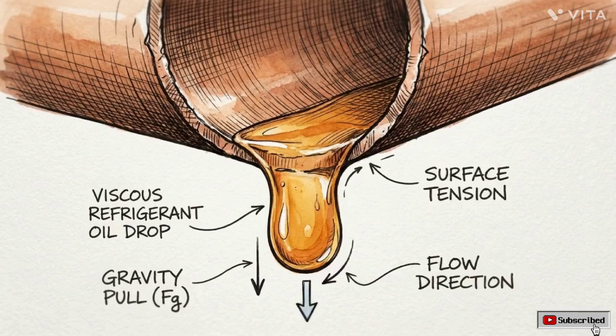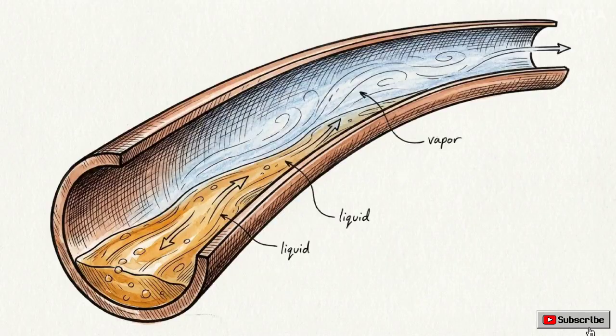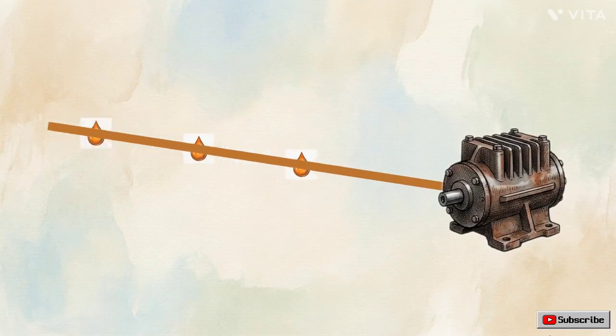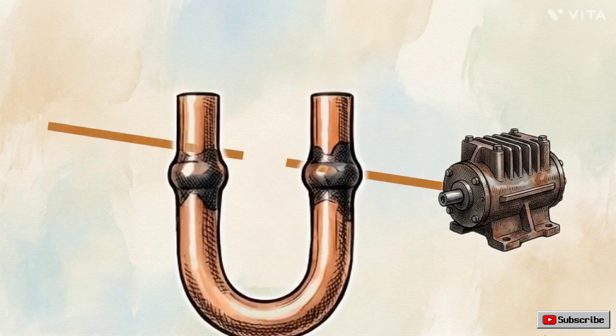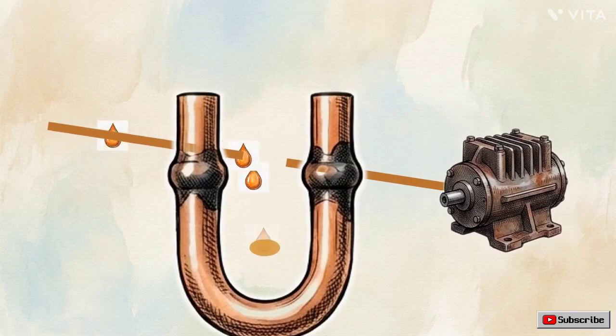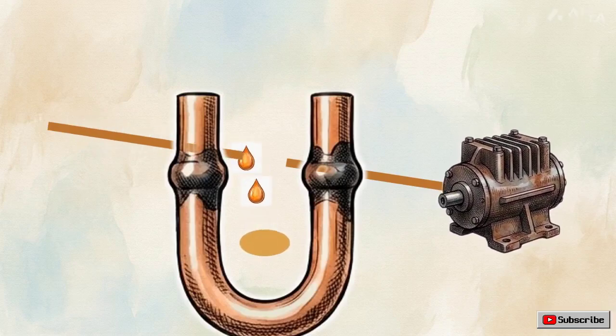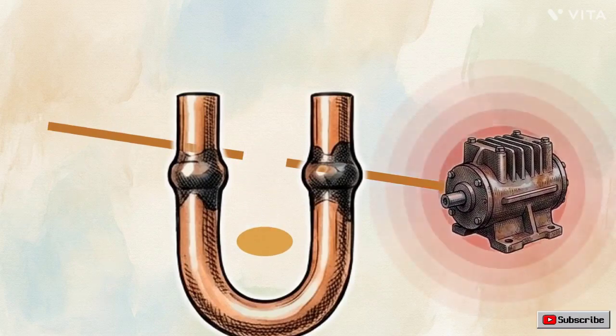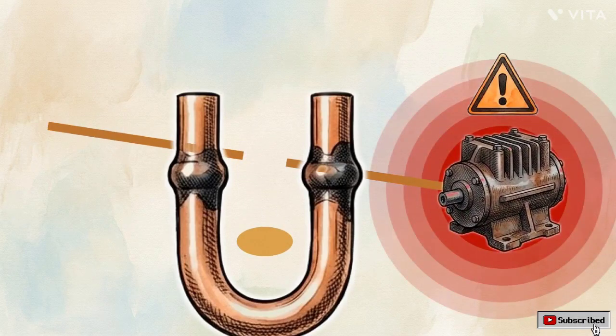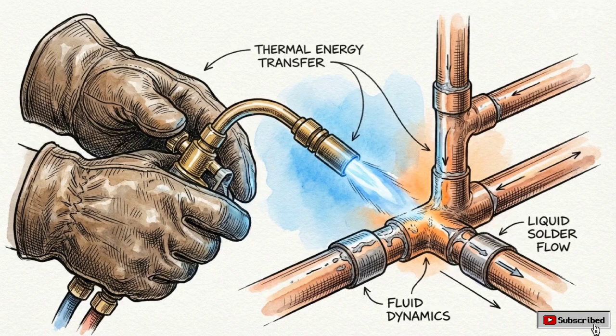The primary physics problem here is oil return. The compressor's lubricating oil mixes with the refrigerant, and it must physically travel back through long, complex piping. When lines are correctly sloped, oil flows smoothly. If an unskilled installer creates a poorly designed vertical curve, the oil gets trapped and begins to pool. As that trapped oil accumulates, the compressor is starved of lubrication. It overheats and seizes. Successful multi-split operation relies entirely on the contractor's mastery of fluid dynamics and precise pipe fitting.